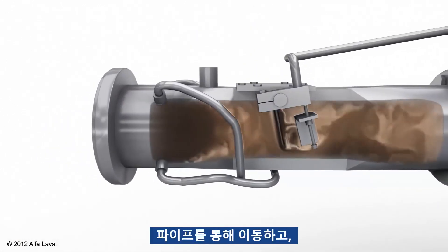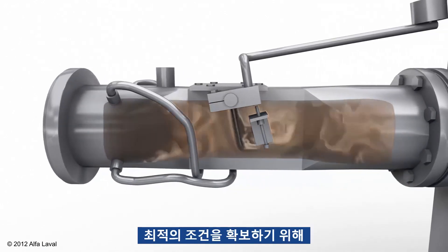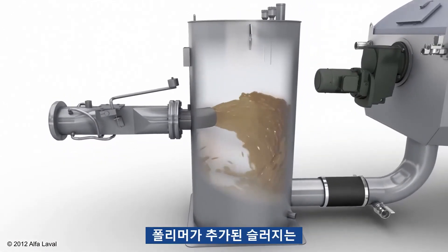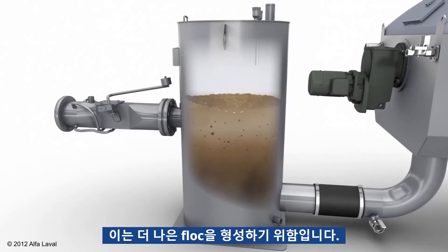The sludge feed flows through the pipe and the mixing valve, where polymer is added to ensure optimal conditions for the polymer to react with the sludge particles. It then flows to the flocculation reactor for extra retention time to mature, which will result in better floc formation.